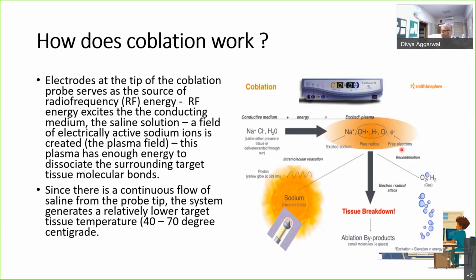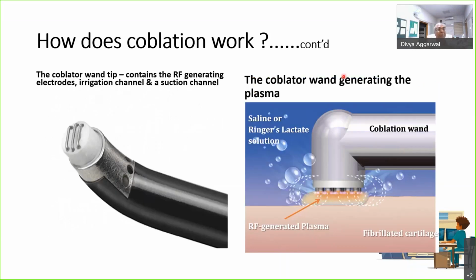And since there is a continuous flow of saline from the probe tip, the system generates relatively lower target tissue temperatures. Now, let me come to the diagram. Otherwise, you won't be able to understand. See, this is the coblation probe. It is known as the coblator wand. And the tip has these three electrodes for delivering the radio frequency energy. And there is a suction channel here, and there is an irrigation channel.